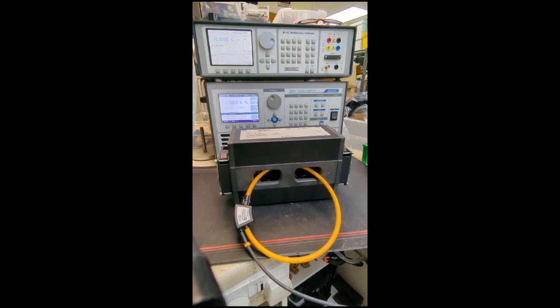Well, in this particular instance, we selected a core with a very, very fine and accurate distribution of the turns on the Rogowski coil. So that means that you have a uniform sensing of the field. This is a crucial part of doing this. Also bear in mind that a Rogowski coil, by definition, is a device that senses magnetic field and rate of change. It does not need magnetizing current like a conventional silicon steel current transformer.